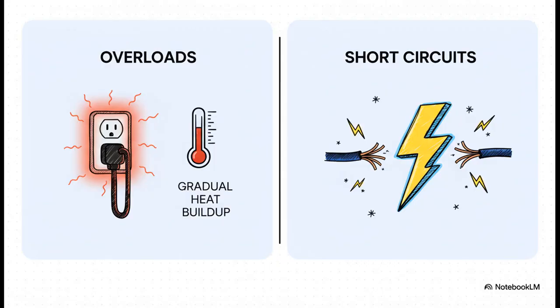So, to really understand our hero, first we have to meet the villains. On one side, you've got overloads. Think of this as a slow, creeping danger, kind of like running way too many things on one circuit for too long. It's this gradual, dangerous heat buildup. And then, on the other side, you've got short circuits. This is the big one, the explosive, sudden danger. A violent, massive surge of electricity that can literally vaporize metal in an instant. Two totally different threats, but they both need one very clever solution.